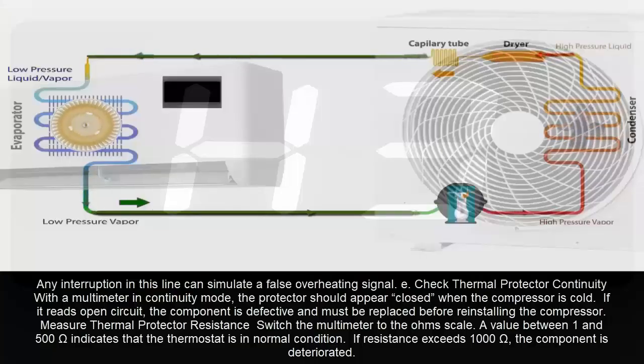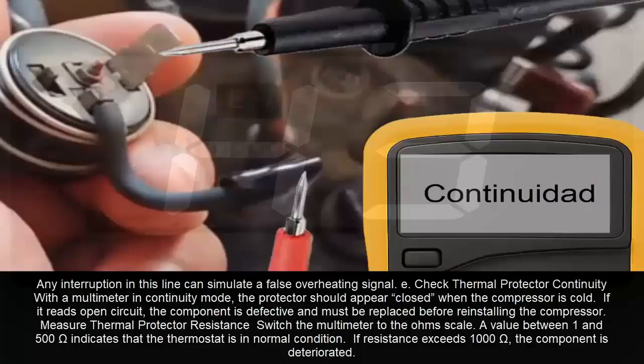E. Check thermal protector continuity. With a multimeter in continuity mode, the protector should appear closed when the compressor is cold. If it reads open circuit, the component is defective and must be replaced before reinstalling the compressor.